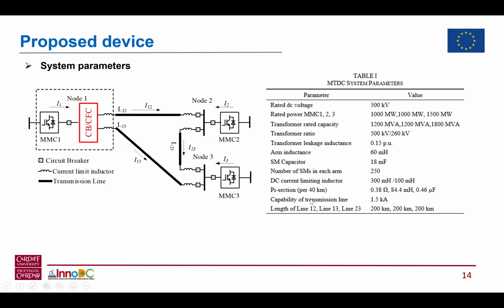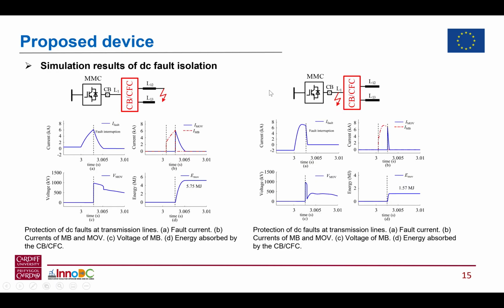And for the simulation results, a three-terminal system has been built in PSCAD. And the parameters are shown in the table. It's a 500 kilovolt system. And in order to verify the DC fault isolation function, artificial faults have been created in both the transmission lines and at the terminals. And from the simulation results, we can see that most of the faults can be interrupted by the proposed device in a very short time.